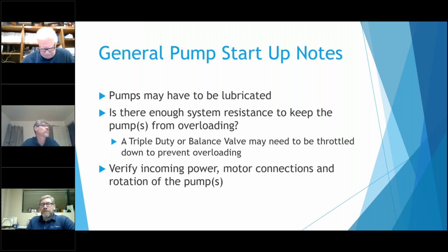You want to make sure that it's wired up properly. You got your 460 wired for 460, or if you got 230 wired for 230. Some of the pumps that they used to have when they were on the motors, it was kind of tough to figure out what the wiring was, and I've seen couplers break because it's not wired properly, or the motor spins too slow because it's wired on high voltage and you got low voltage coming in. So you want to double check to make sure it's wired properly before you turn that on.